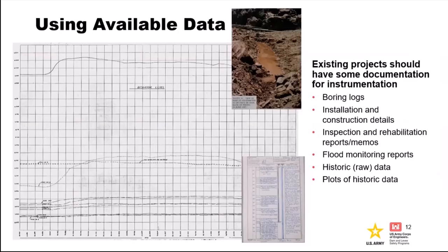This time history plot here is showing piezometers, and it's the only record we had available for the time shown, 1 year. I think this is for Abiquiu Dam, actually, which Amy talked about yesterday. These instruments were read manually, and the original instrument readings could not be located. There's a hard copy somewhere where Buddy was out there in the field recording these water levels, but we could not locate it in our files or in the archives in the case of Abiquiu.